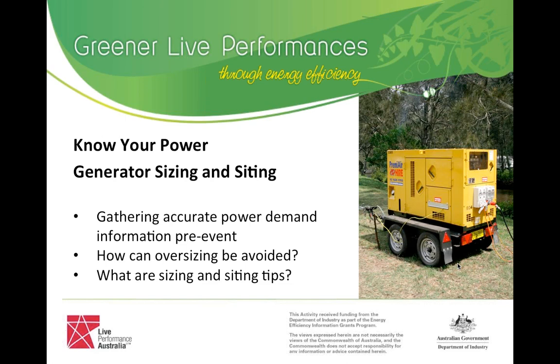We'll hear hopefully from some generator techs about the effects on fuel consumption when you have a smaller number of larger generators that perhaps aren't being fully utilised, because we see the reverse happening in some scenarios where the most efficient option is actually to have more, smaller generators. That enables you to power them completely down when they're not needed. Both solutions are relevant, but it completely depends on your scenario, which makes giving advice very tricky because every single event scenario needs personal attention.